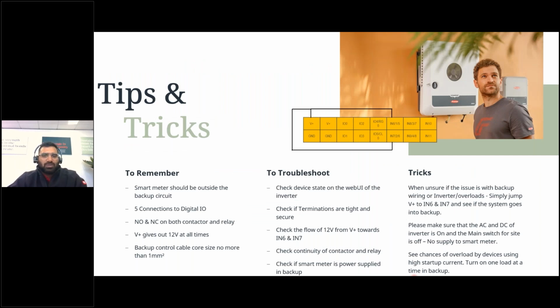So tips and tricks, what can we keep in mind when you are building a backup circuit? Things to remember, the smart meter should be outside the backup circuit. So when we are running the system in full backup, the smart meter should not get power supply. What would happen is that when the system power supplies the smart meter, the smart meter is what tells the inverter the grid is back on again. So as the smart meter gets power supplied, it would send the signal to the inverter that the grid is back again, and the inverter will just restart, resetting all the contactors and relay to grid connected mode. And that's how the system is reconnecting to the grid.